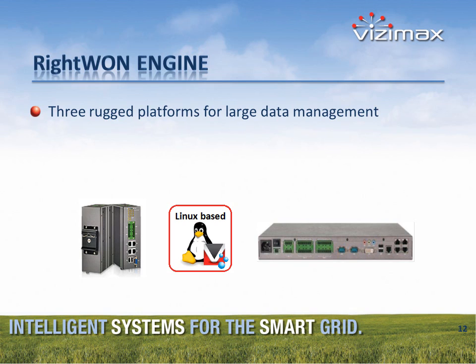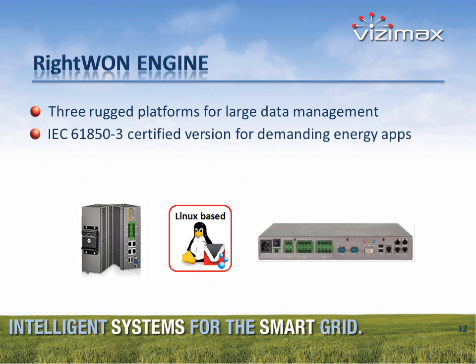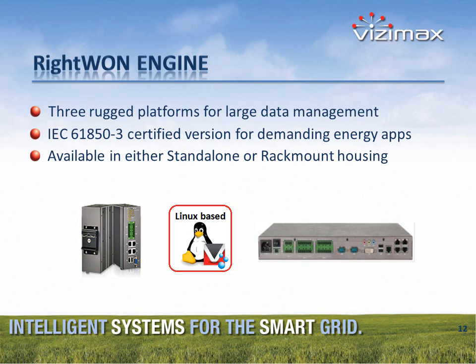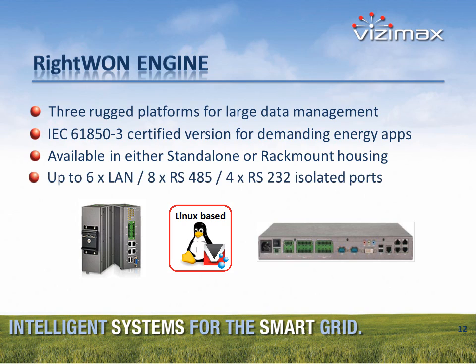Besides the RightWON satellite, I also mentioned earlier that we support the RightWON engine. Actually, we support 3 platforms, and these platforms are mainly used for more demanding energy applications. They are mainly used for either communication-oriented application or substation automation. It's available either in standalone mode that we can mount on a DIN rail or a rack mount housing. The unit is available with up to 6 local area networks, up to 8 RS-485 channels, and up to 4 RS-232 isolated ports. So various configurations are available, and these units can generally handle up to 10,000 points.